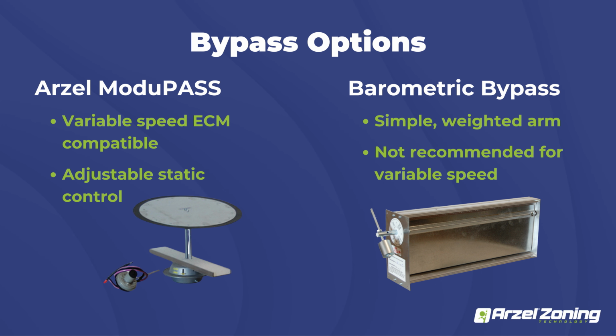So to get rid of that, Arzel came out with the modulating bypass, which, in the picture on the top there, has a little transmitter right next to the damper itself. That's going to read your static pressure in your ductwork, and then it has a little control knob on the top. Once you dial in whatever static you want to maintain on that system, it's going to modulate that damper to maintain that specific static across that whole system. So it's a lot more precise control as far as bypasses go. And it also gets rid of that hunting that we get with the barometric as well. Cost-wise, they're not that much different. I would just spend the extra couple bucks and go with the modulating bypass, and just know that I have a better controlled static pressure achieved.